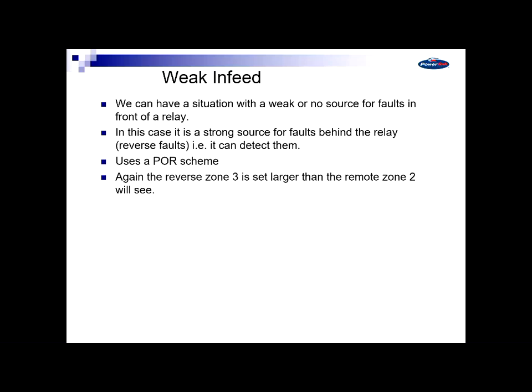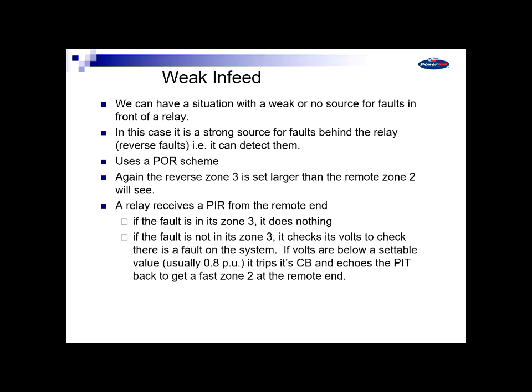There's zero sequence sources on some of the transformers, but for phase current, there's not. So you're weak. But for faults behind you, you're strong because you've got the same source I've got, just a bit of a distance between us. So you can see faults behind you, you can't see faults in front of you. So the way we set a weak in feed, it's just a setting in the relay, you tell it it's weak in feed, it says, all right, that's just a feature.